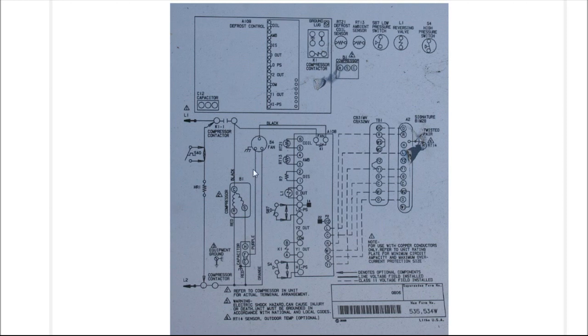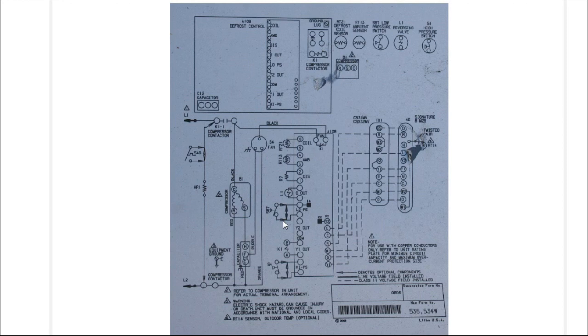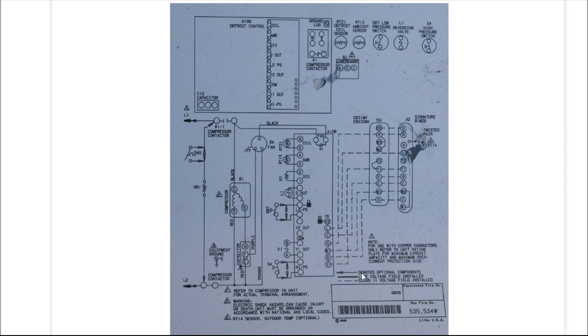This designates an arrow right here as well. Those are optional components. So if you're working on a Lennox system like this and the ladder diagram shows that it has a low-pressure switch and then you look in the equipment and there isn't one, don't freak out. That's just because it didn't have that option. They use these schematic diagrams and ladder diagrams for several different units, so they don't have to print out three or four different ladder diagrams.